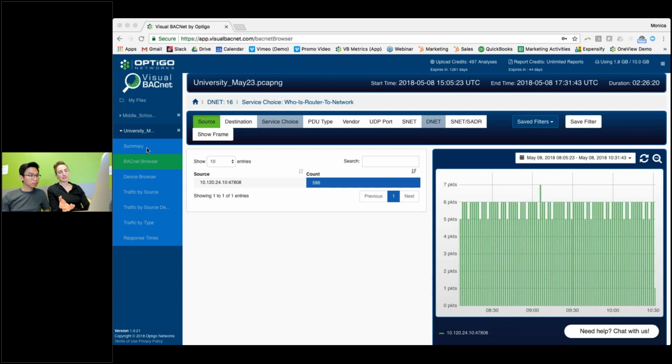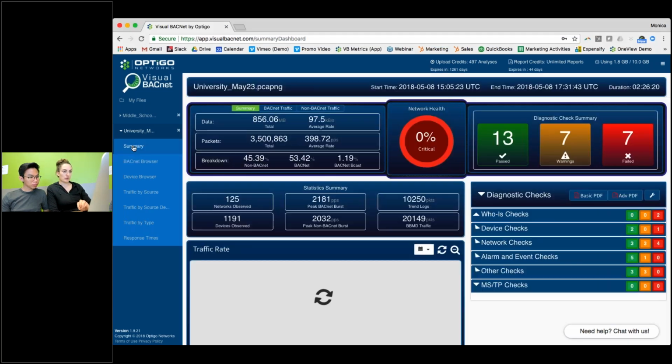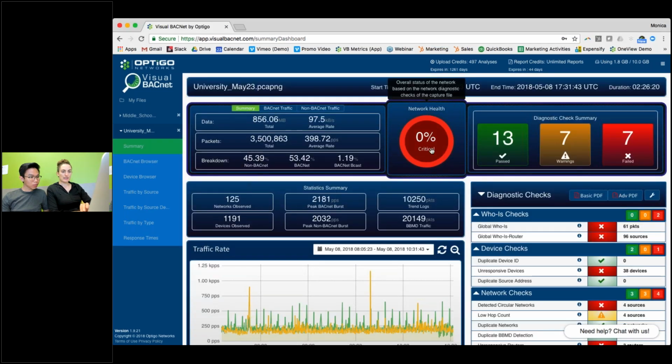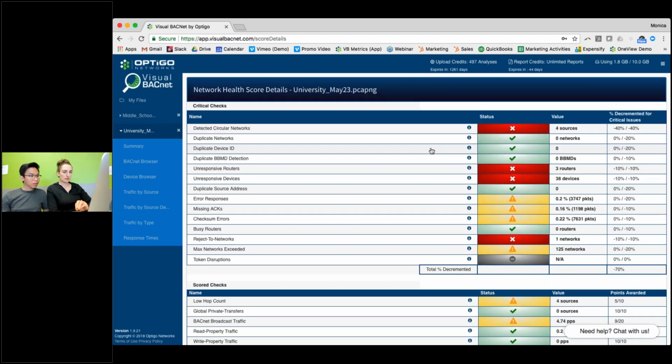Otherwise, you're going to get to a situation like this where you go, okay, it's all coming from this BBMD, it's underneath, now I have to go capture there. So you may still end up doing that, but the more you know about where it's coming from, then you can kind of go, oh, these paths all have trouble and they all go through this same device. Okay, so something underneath that NAE is causing problems.